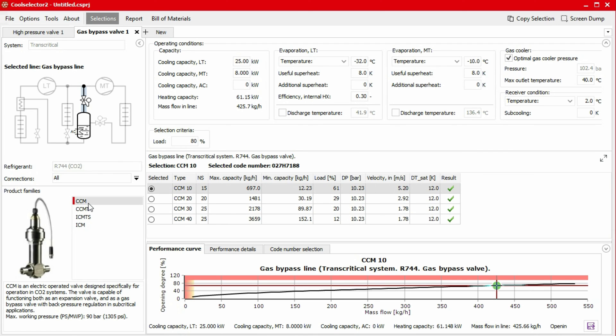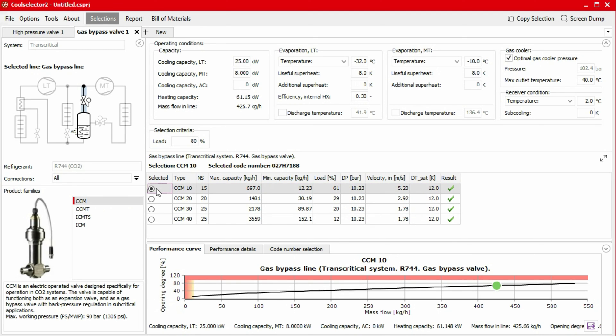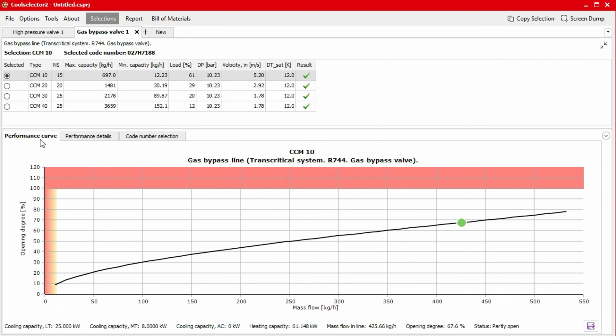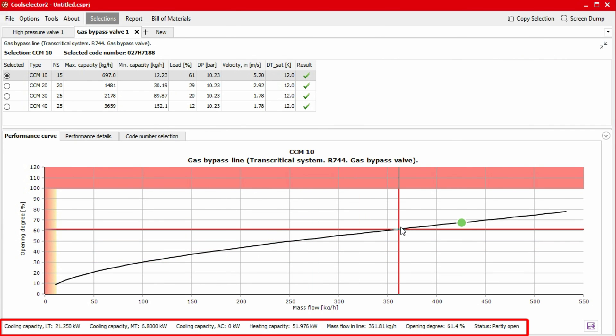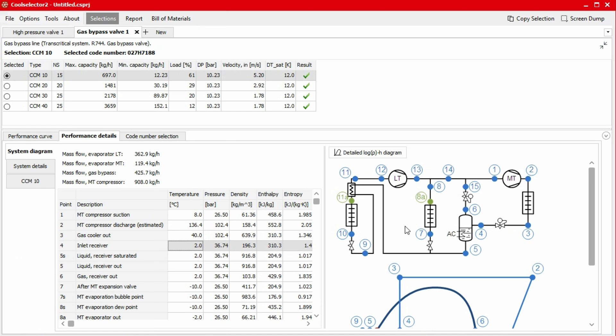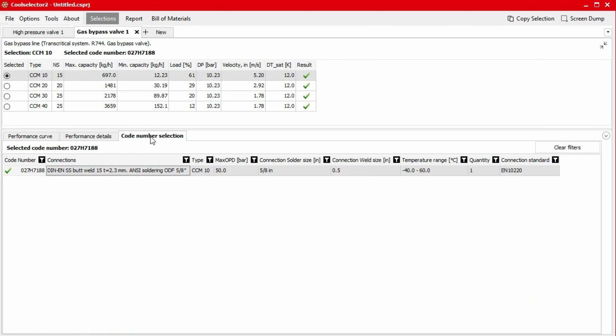The main window will now refresh to display product information. You'll notice that one row is highlighted in green — this is the product suggested by the application as most compatible based on capacity and load. This is only a suggestion and you should check the performance details to decide if this is best for your system. To check the performance details, we head to the bottom-most segment of the window. In the first tab titled Performance Curve, you'll find an interactive graph plotting the opening degree against mass flow rate. The values will update as we move our mouse across the graph. Under the performance details tab, we can find the thermodynamic data for the system along with a system schematic and a pressure enthalpy chart. In the sub tabs, we have system details as well as product specific data. Under the code number selection tab, we can find code numbers as well as some additional product information. We can then generate a report as well as a bill of materials which can be provided to a Danfoss supplier for a quotation.